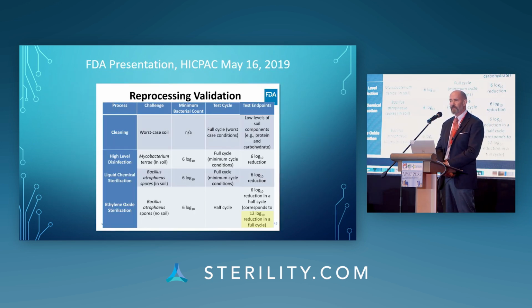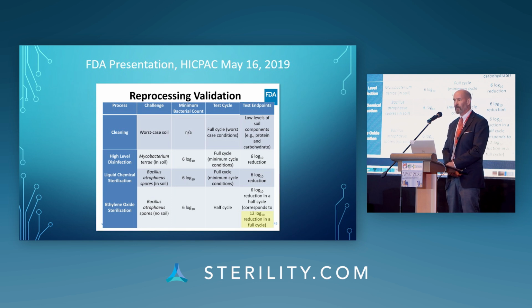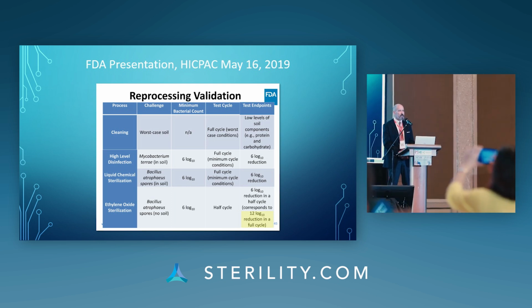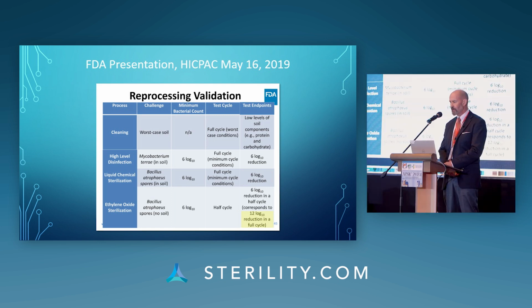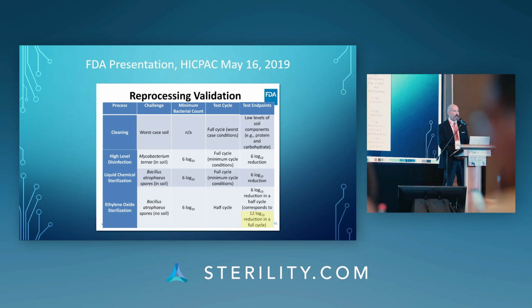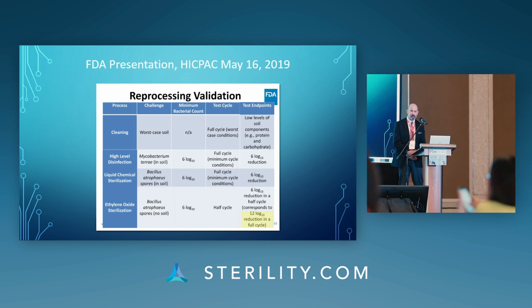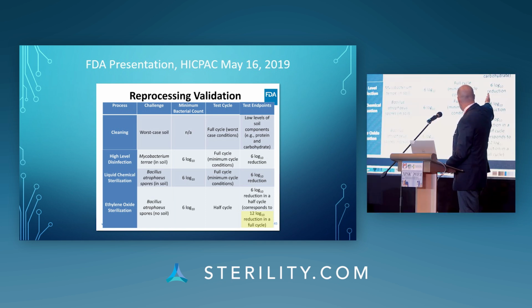In this 2019 conference, FDA published this validation study. And this study really quantifies the difference between high-level disinfection, liquid chemical sterilization, and ethylene oxide sterilization. And I'll draw your attention to the column here on the far right.